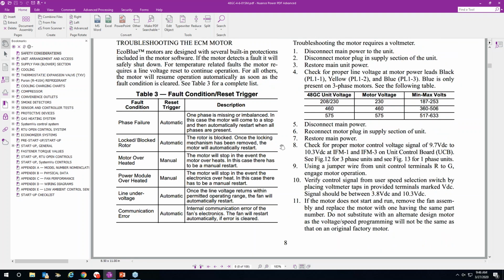But what we're finding is that high leg delta, which is not real common everywhere, but there are some older power supply, older infrastructures in the greater Chicago market that have that high leg, and it has caused nothing but havoc on the VFDs. Now we're finding that high leg does cause problems on these motors. So what do we do? Well, what the factory's done now is they've gone back to the motor manufacturer. The motor manufacturer says, yeah, we kind of knew about all that, which was just wonderful, right?